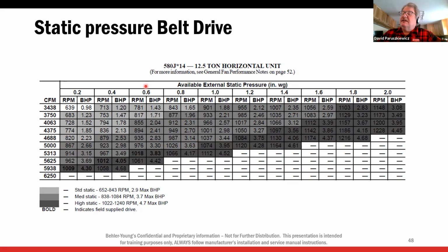So anyways, let's say I have 0.6 inches of static. I have to adjust it accordingly. I have to adjust my RPM accordingly to get the static I need. So, I have to adjust that belt accordingly for the static I have. But again, if I need to get above, in this case, the 0.8 inches, I need to go to the 1 or 1.2 inches. I have to change the drive.